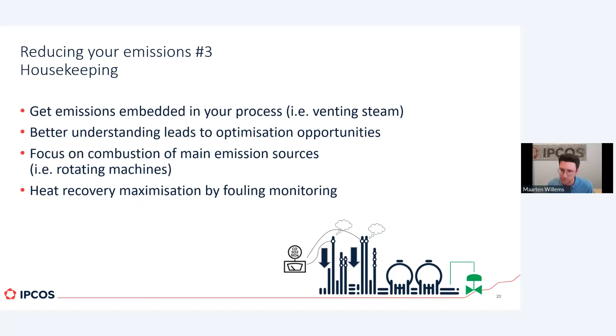Now, when we look at fouling of your heat exchanger, it's a fouling monitoring example. What is fouling? Fouling is, in a heat exchanger, a measure of sediments that stay behind from the process flow on your heat exchanger. The result of these sediments is that the heat exchanger efficiency goes down.